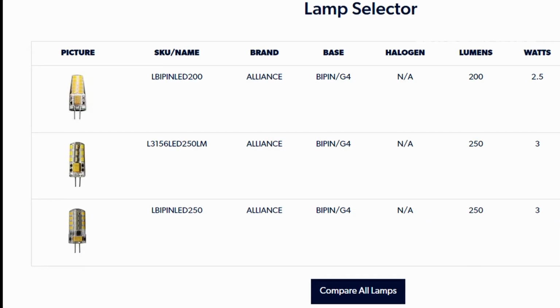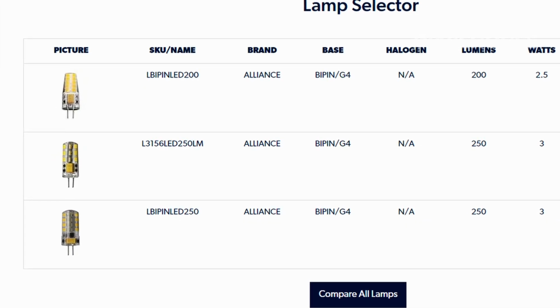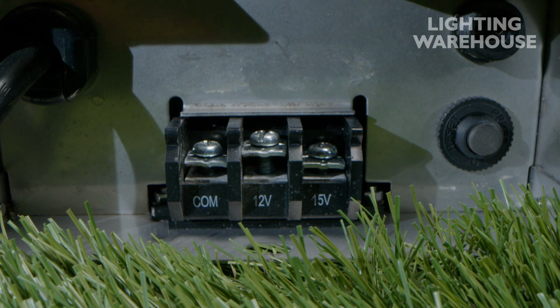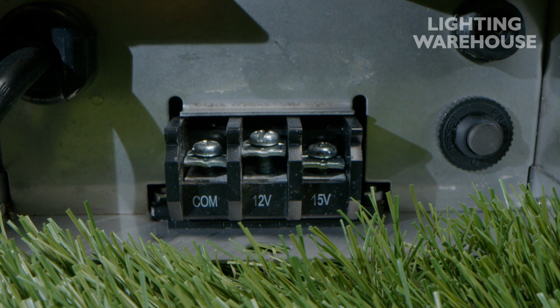As far as power goes, you get a lot from a little with LED bulbs. They are the most commonly used type of lamp these days. They draw less power, have more options, and last longer than the old standard halogen bulbs. Many times you'll find transformers with a single 15-volt tap. However, there are transformers that have multiple taps that might be anywhere from 10 to 15 volts.